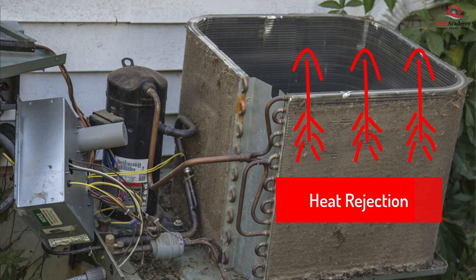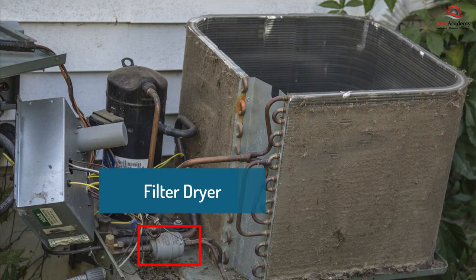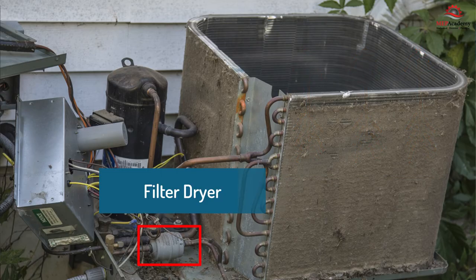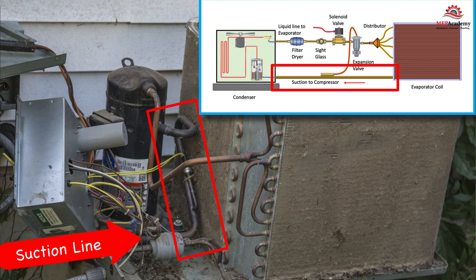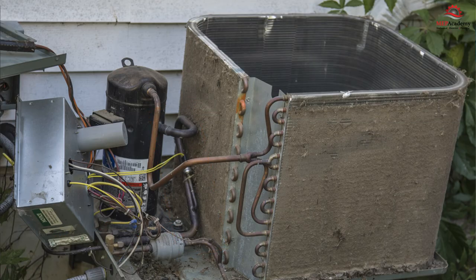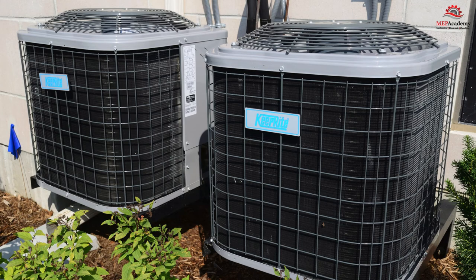But in this poor condition it won't be working. Here is the filter dryer that's on the hot liquid line leaving the condenser and sending liquid to the expansion valve at the evaporator. Here is the suction piping that has arrived from the indoor evaporator section and is entering the compressor below the discharge piping. Here is what the condenser may look like from the outside.